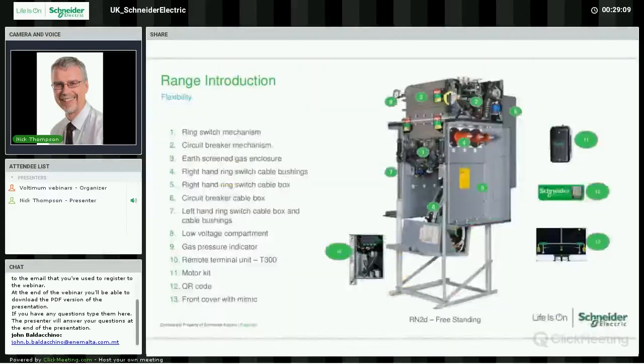When we look at the various product features, the architecture and the look of RN2D has changed. Well, the look has changed a little bit. The method of operation is no change at all. The gas enclosure looks very, very similar, with the exception of Type C bushings, which are now fitted. But we've still got the various standard things like gas pressure indicator. Motor kits are still available. It's the same motor kit that is used in RN2C.